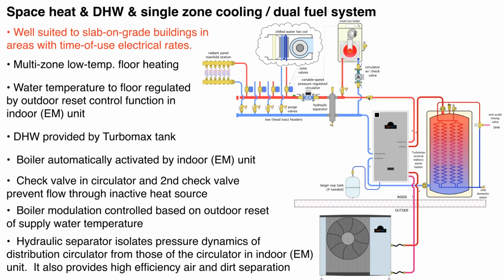It doesn't really matter whether it's an integral check valve in a circulator or whether it's a separate check valve. I tend to like spring-loaded check valves over what are called swing check valves. The swing check valves are okay, but they have to be mounted in a horizontal position. And with any check valve, a good detail is to provide at least 10 pipe diameters of straight pipe upstream of that check valve. The idea is that you don't want highly turbulent flow going into the check valve. That could cause the mechanism in the check valve to rattle a little bit. So again, it's just a little hydronics 101 detail. Put some straight pipe out in front of those check valves when you install them. So that's the dual fuel application. Again, that would be a specific model of the Advantage indoor unit.